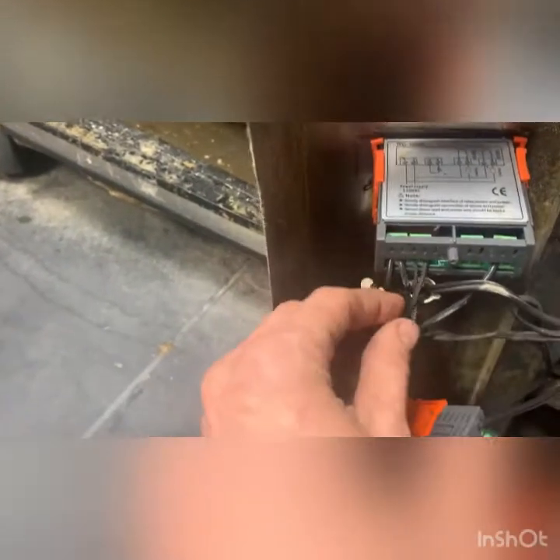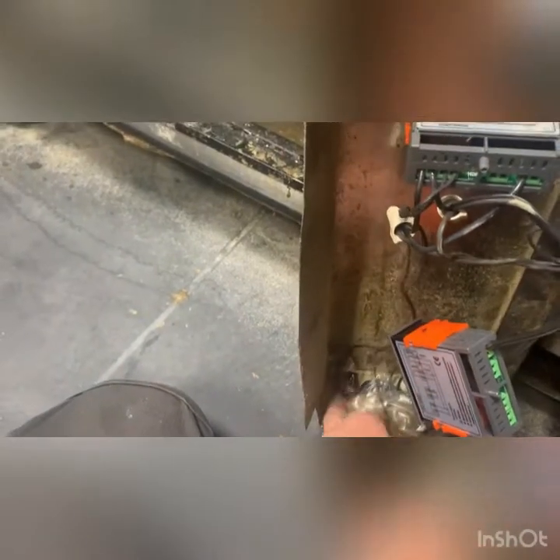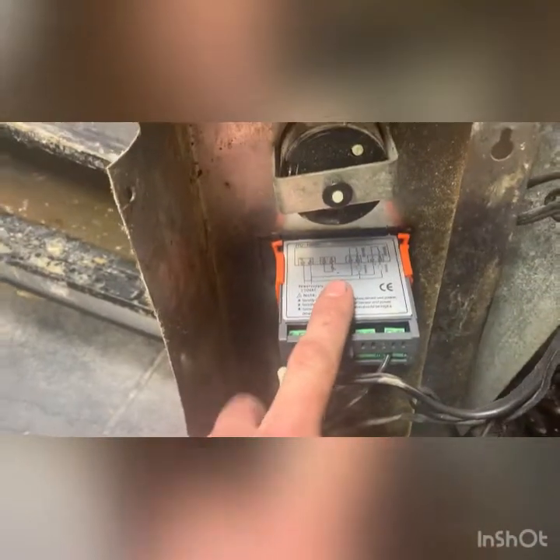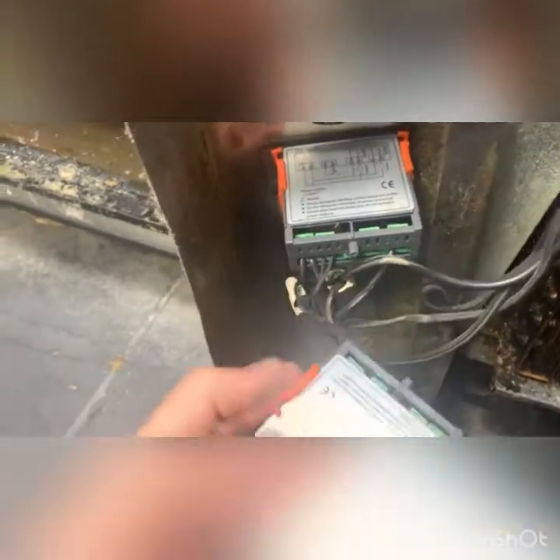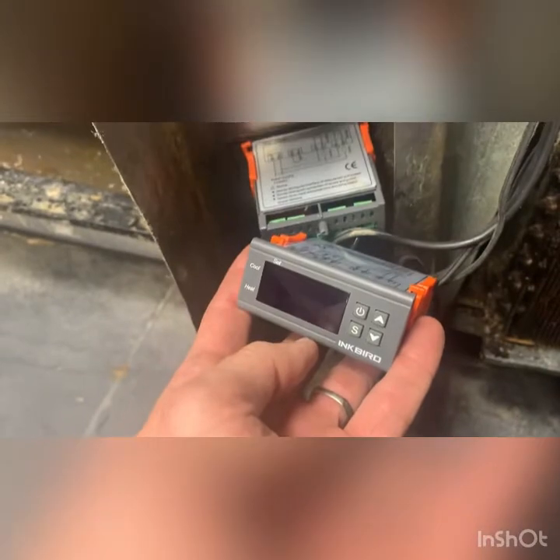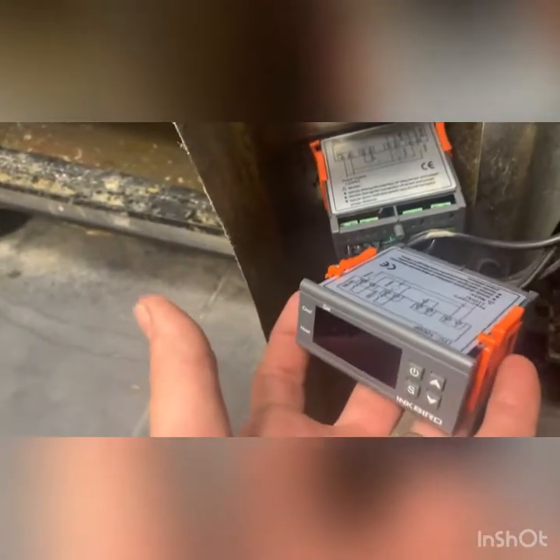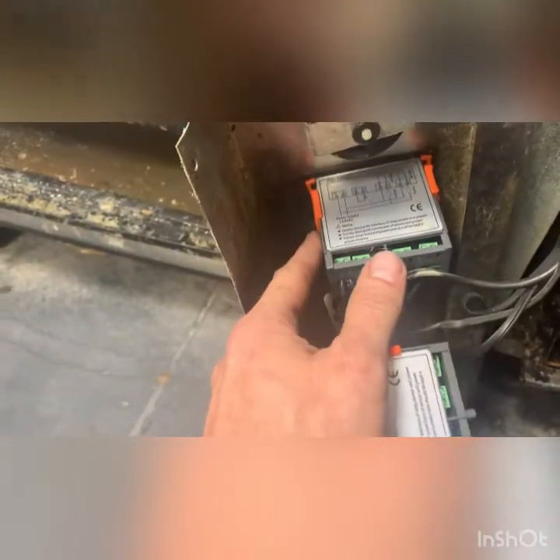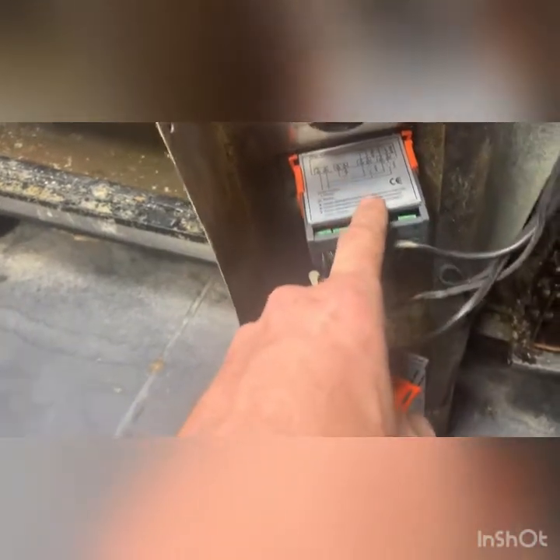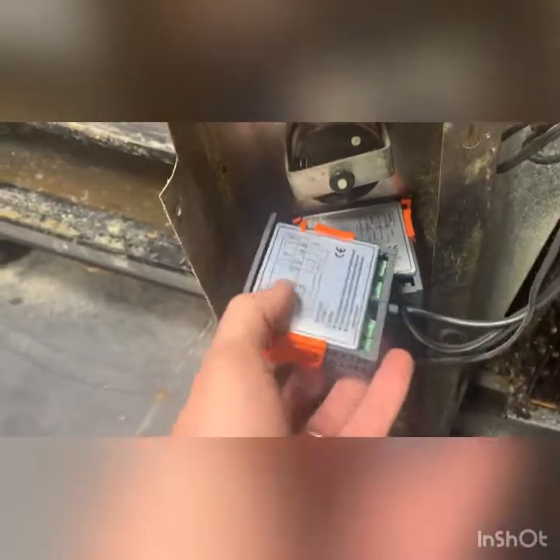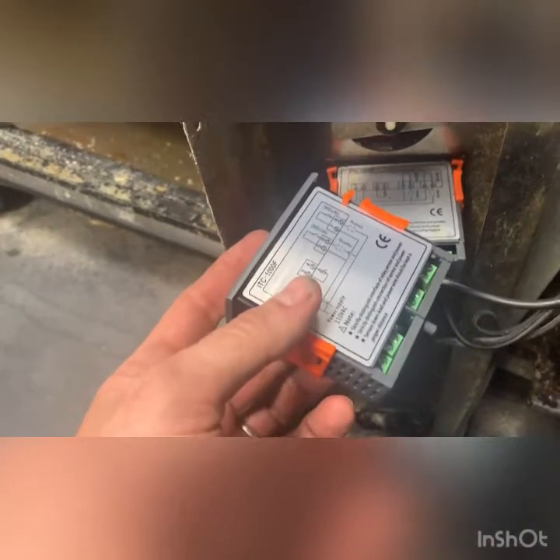I've taken some pictures. What I'm going to do is wire for wire everything into this, and then we'll replace them. The possibility also exists that the actual temperature probe is bad, and that's why I'm getting the 16 below. But if that were the case, the unit still wouldn't be freezing. So I'm not going to open up the unit and check the probe. I'm going to hook up the new controller with all of the existing setup, and I believe it will work properly then. If it still gives me a stupid low temperature, then we'll have to chase back the probe and replace it. But the intelligence is in here, not the probe. We're going to go with the easy and most statistically solvent solution first. So wire for wire, one at a time, and we'll get her in place.